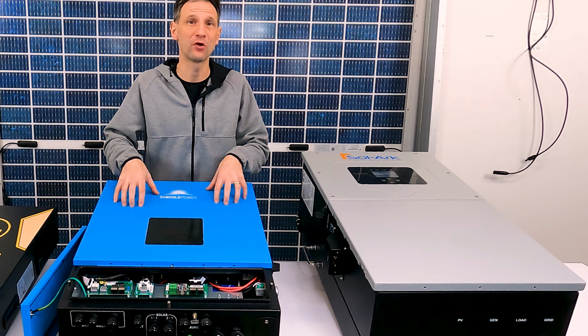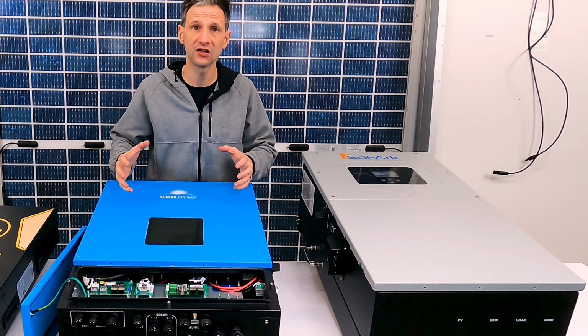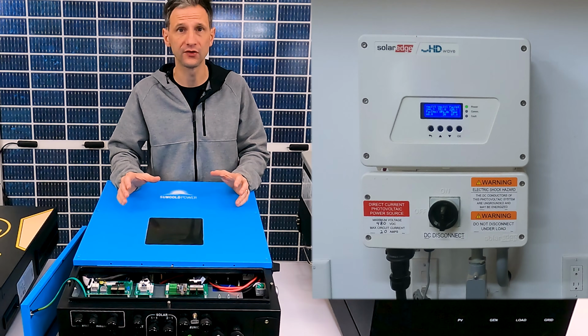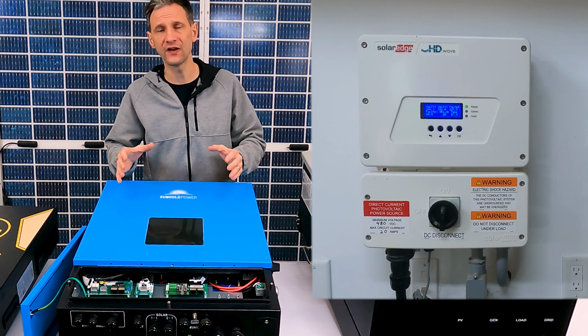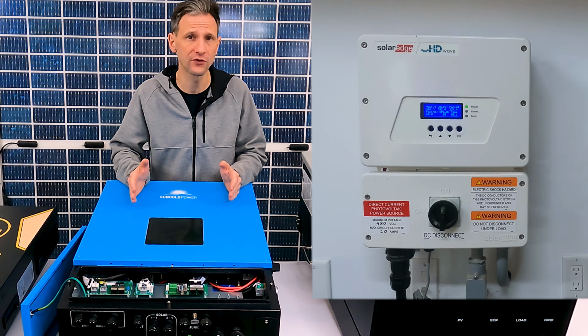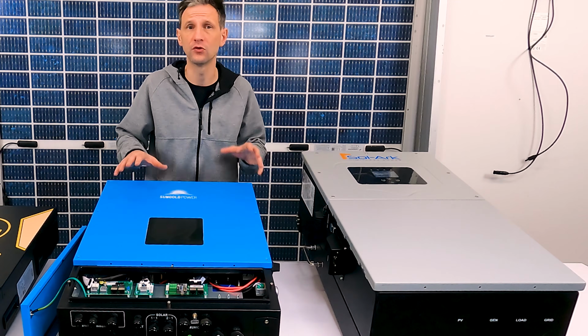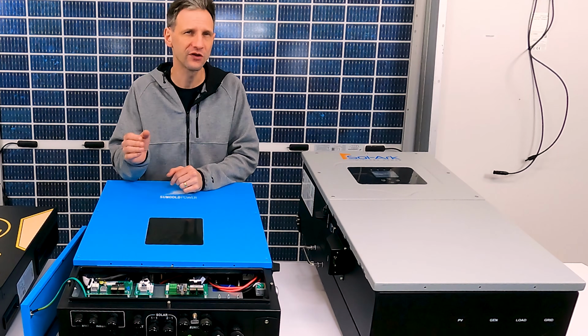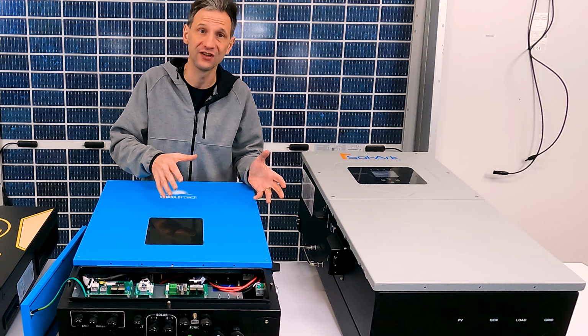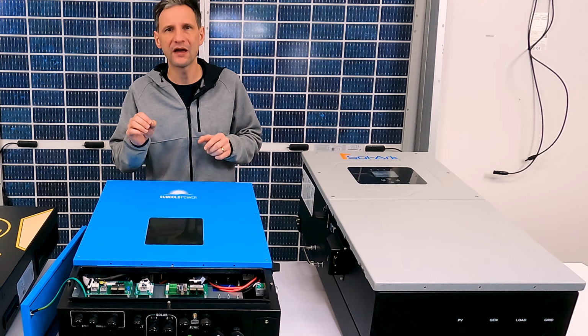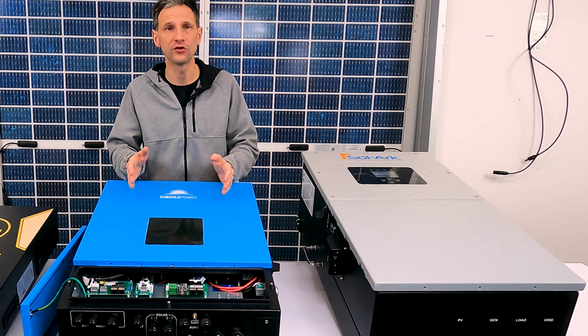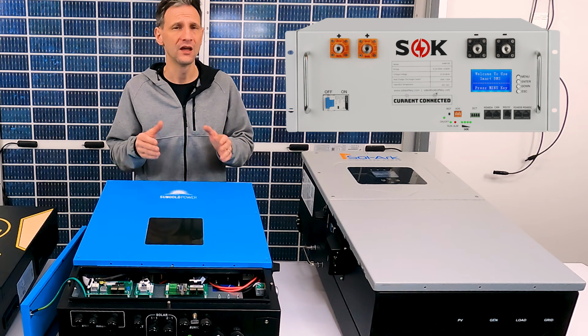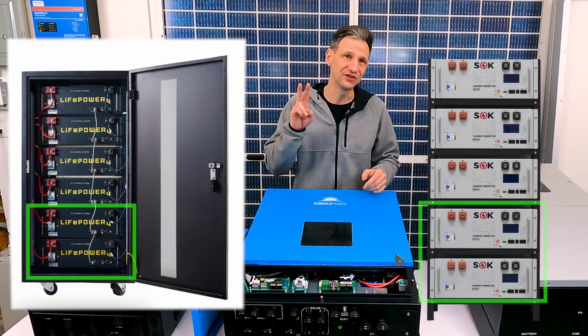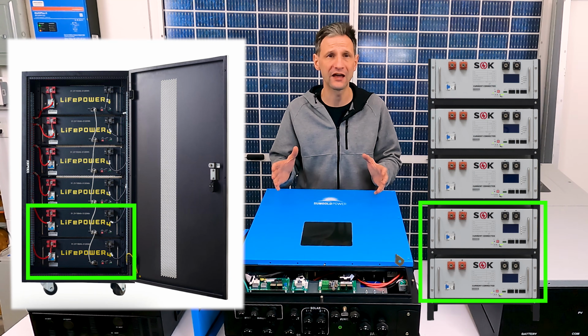Another great feature for this price point is the capability of AC coupling with existing PV inverters. That will allow you to take advantage of the power from a grid tie inverter that would normally be unusable in a power outage. Be sure to confirm compatibility with your existing inverter. If you're adding battery storage, you will need to pair this inverter with a 48-volt battery. Again, I would recommend starting with at least 2 48-volt server rack batteries.